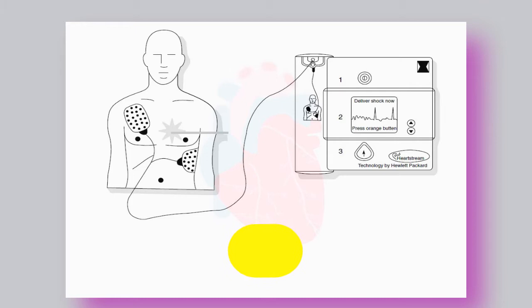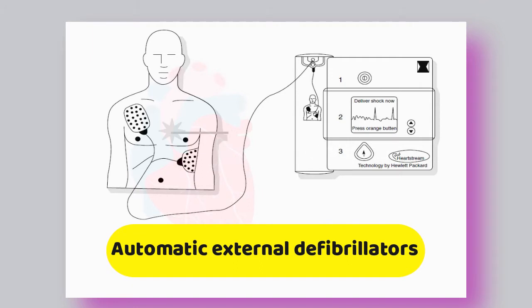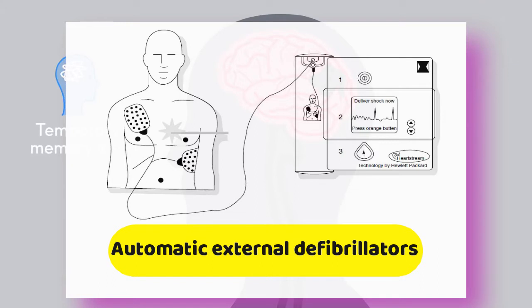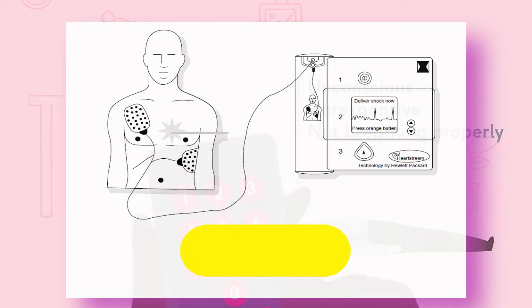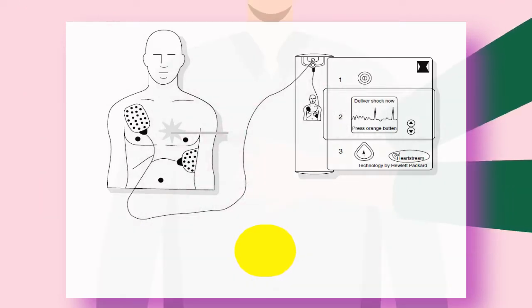Let's begin the video with Advisory External Defibrillators or Automatic External Defibrillators. An important development in the field of defibrillators has been the development and successful use of Smart, Automatic or Advisory External Defibrillators, which are capable of accurately analysing the ECG and making reliable shock decisions. They are designed to detect ventricular fibrillation with sensitivity and specificity comparable to that of well-trained paramedics, then deliver automatically or recommend an appropriate high-energy defibrillating shock.